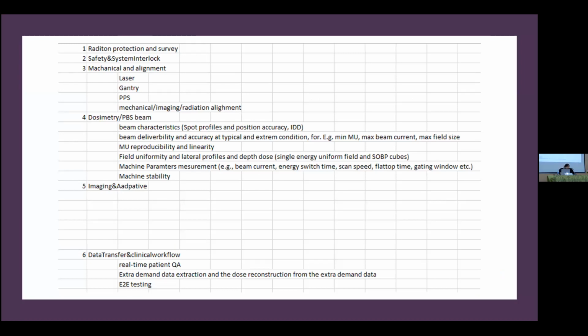This is a screen capture of different things that we test. So we already talked about radiation protection and survey. Something else that the regulators would be interested in, maybe not the radiation regulators, but there's many different types of regulators, they'll be interested in the safety and system interlocks. For example, if I try to walk in here, it should turn off the beam because I shouldn't be in there, these kind of things. And also of the actual radiation going to the patient, that the machine can actually turn itself off if something was going wrong, or these kind of things. Same thing on your regular linear accelerator. If there's some type of collision, does it properly stop? All these kind of things. Those are some of the regular safety things and aren't necessarily radiation specific. But knowing how those operate.